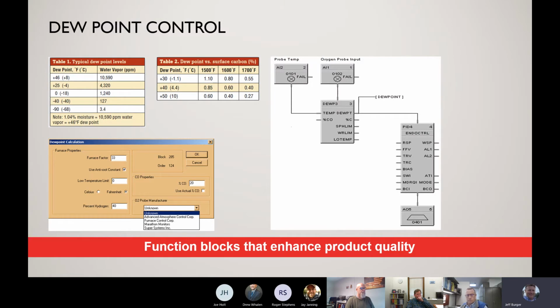Another out-of-the-box function block is the dew point control. Again, this would be for more of the heat treat applications. You can see down here on the bottom where it says O2 probe manufacturer. Again, you can select the probe manufacturer from several different companies. You select that, and then the dew point control block will understand what the probe is that's hooked up to that system. You can see that it talks about typical dew point levels and dew point versus surface carbon percent. This algorithm is used a lot within heat treat applications, and it really enhances the functionality you can have for that application.